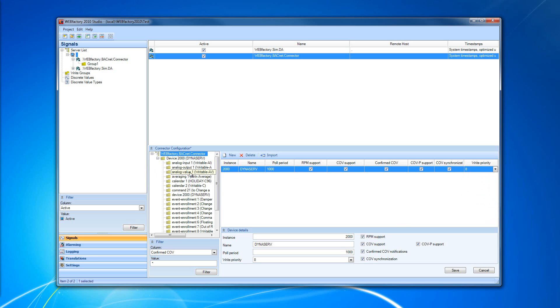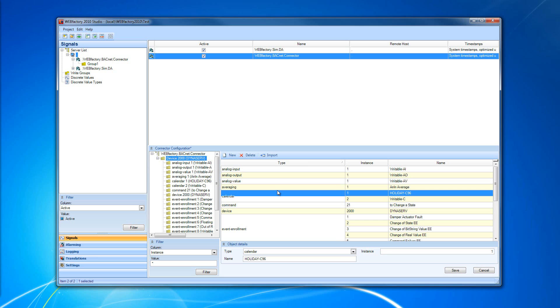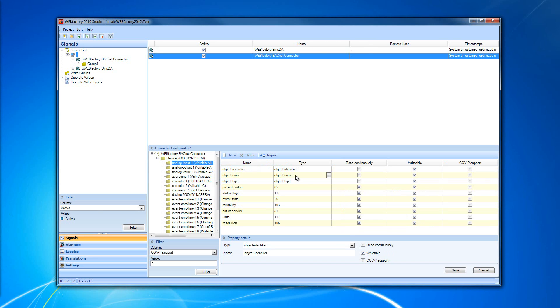When selecting the BACnet connector in the navigation tree on the left side panel, all the BACnet device properties we discussed are displayed in the main view of the connector configuration. When selecting the BACnet device, the instance, name, and type of the BACnet objects are listed in the right panel. And if we select a BACnet object, the name, type, read, writable, and COV support will be listed in our property grid.